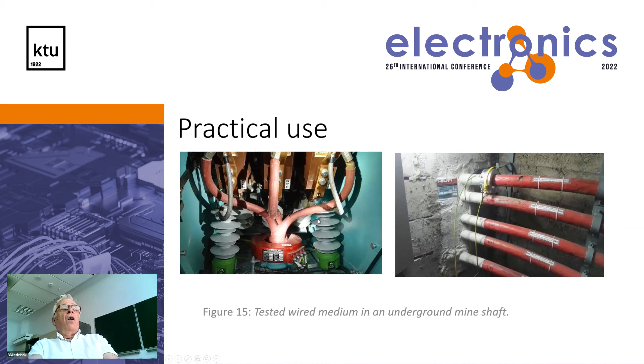Here are the couplers employed on the two phases. In this case, there is only one inductive coupler. Therefore, for this purpose we use a 3-phase cable, about 3 meters long, which is located in the mine shaft headroom selected. The cable was a part of a tested medium voltage network of 6 kilovolts, with a total length of about 1,300 meters.